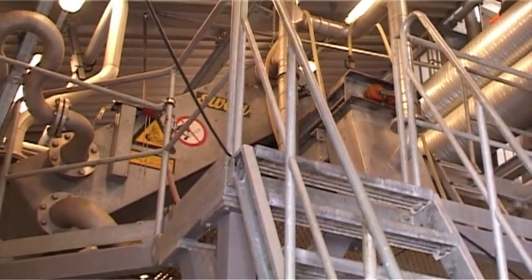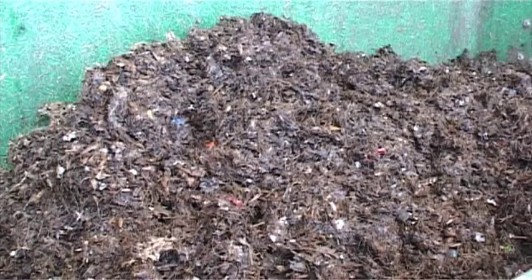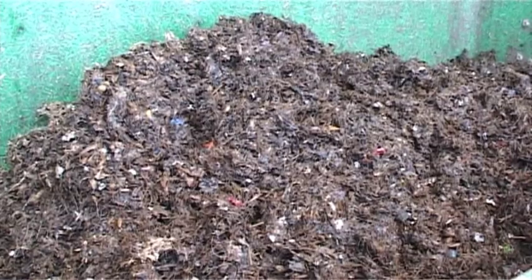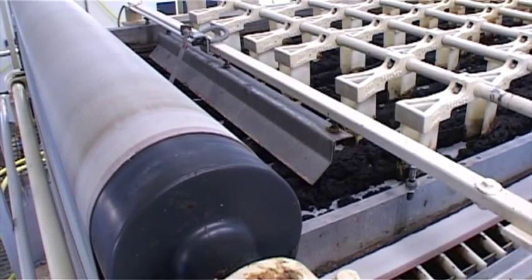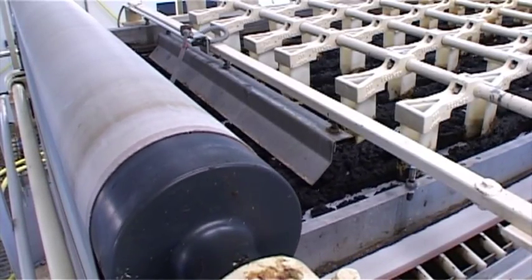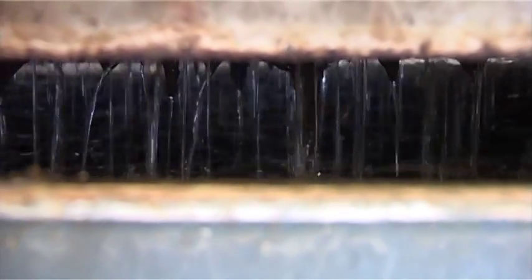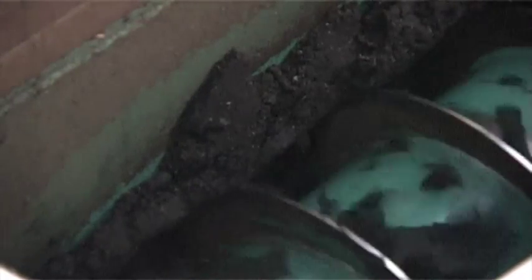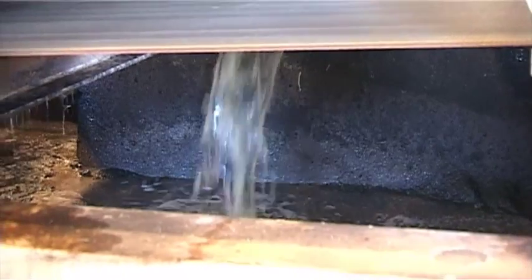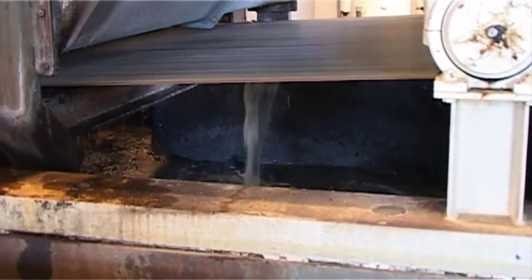From the heat exchanger system, the slurry is pumped to a sieve, which filters any remaining contaminants out before pumping it onwards for dehydration. The slurry is dehydrated by addition of a substance which separates solid particles and water. Dehydrated slurry becomes a dry substance of approximately 24% total solids and is pumped to storage. The drained-off water is passed along with wastewater to a purification plant on the same site.